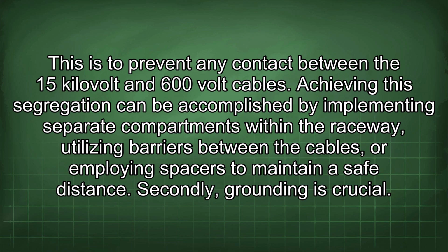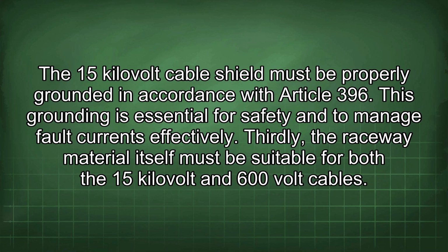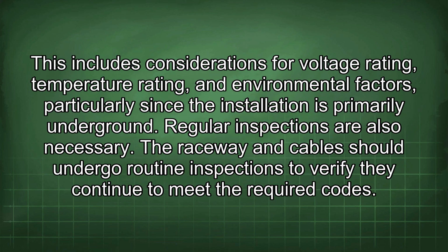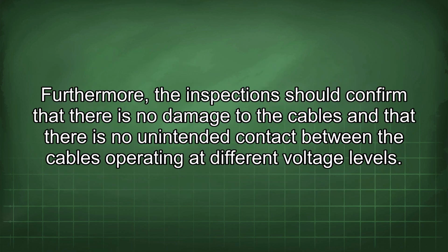Secondly, grounding is crucial. The 15 kV cable shield must be properly grounded in accordance with Article 396. This grounding is essential for safety and to manage fault currents effectively. Thirdly, the raceway material itself must be suitable for both the 15 kV and 600 V cables. This includes considerations for voltage rating, temperature rating, and environmental factors, particularly since the installation is primarily underground. Regular inspections are also necessary. The raceway and cables should undergo routine inspections to verify they continue to meet the required codes. Furthermore, the inspection should confirm that there is no damage to the cables and that there is no unintended contact between the cables operating at different voltage levels.